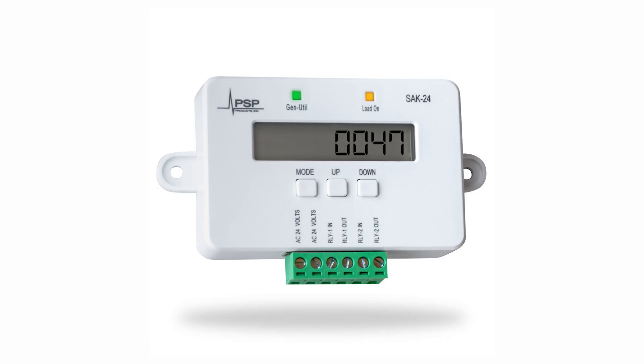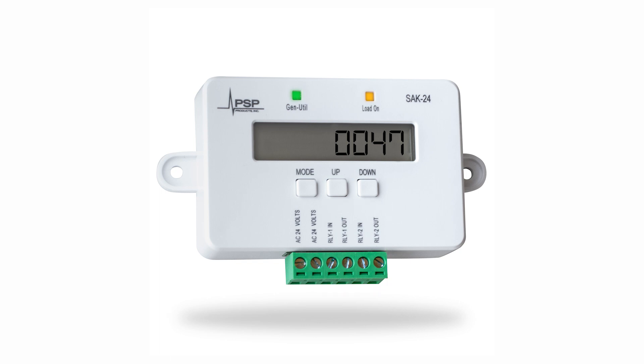The SAK24 allows load management of HVAC systems on a standby generator using the low voltage HVAC control circuits. It is powered by 18 to 30 volts AC, sourced from the low voltage transformer in the air handler. It has two sets of dry contacts that open and close together. The settings on the SAK24 are grouped by application, called master modes.